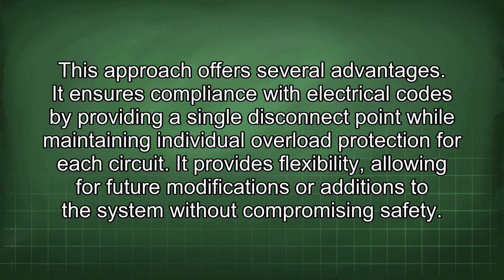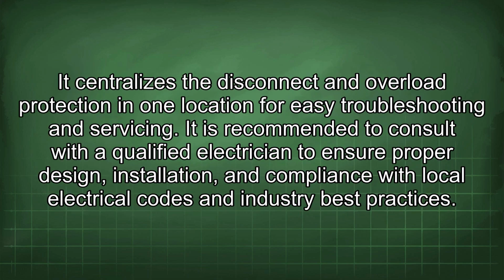This approach offers several advantages. It ensures compliance with electrical codes by providing a single disconnect point while maintaining individual overload protection for each circuit. It provides flexibility, allowing for future modifications or additions to the system without compromising safety. It centralizes the disconnect and overload protection in one location for easy troubleshooting and servicing.